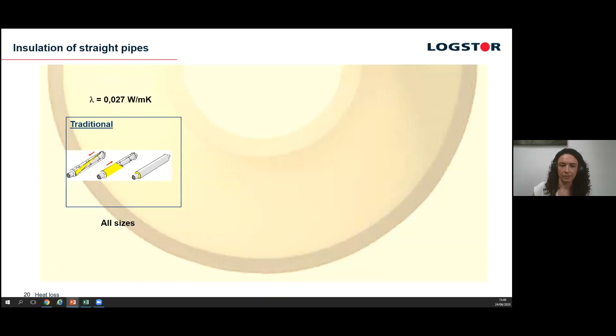And then on larger diameters over 315, we have the spiral conti, which is where it's effectively sprayed onto the pipe as it goes through the machinery. And then if you look at the corresponding lambda values, you can see that the axial conti there is giving you the greatest reduction in heat loss, followed by the conti, and then the traditional.